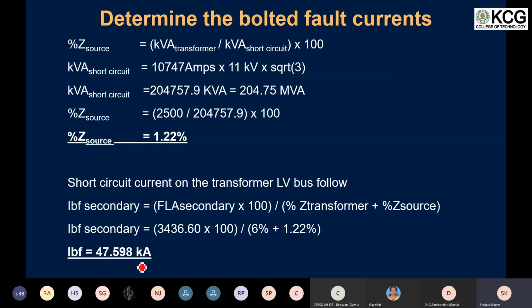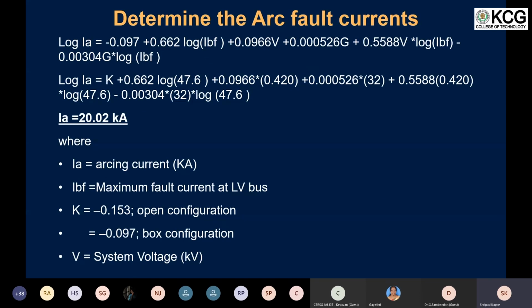And when we use the IEEE 1584 standard to convert that bolted fault current and to understand the associated arc flash current, that arc flash current was near about 20.02 kiloamps level. In the calculation of this, we took into consideration the maximum bolted fault current and the system voltage, which in this case was the 415 volt system voltage, and the configuration of the bus bar, or the configuration of the total cubicle that houses the breaker and the bus bar.